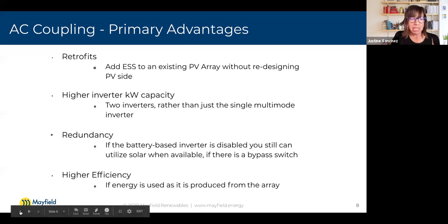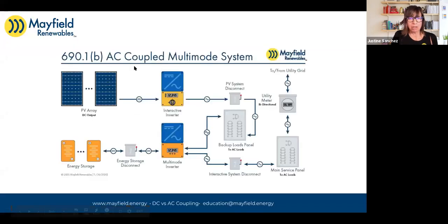So in the AC coupled situation, here's our AC coupled situation. Our interactive inverters are commonly more efficient than our multi-mode inverters. So if you're utilizing the power as it's being produced, and you're not running it back through this multi-mode inverter to charge batteries and then back through, say at night, and you're using it during the daytime, you get to take advantage of this higher efficiency inverter, essentially.